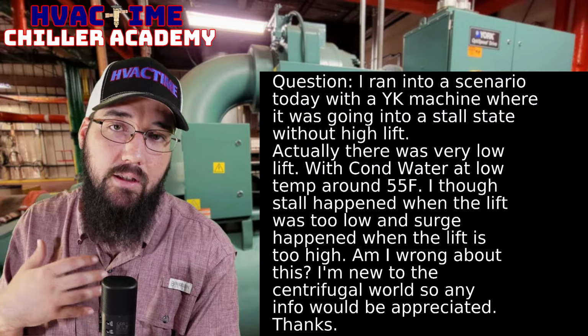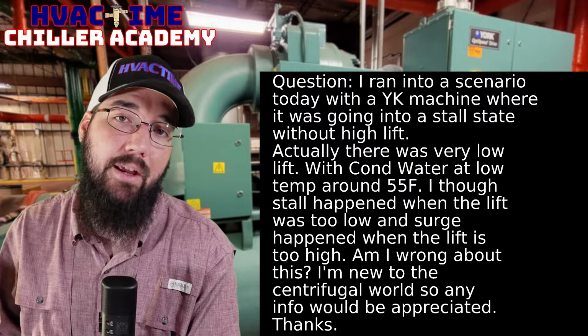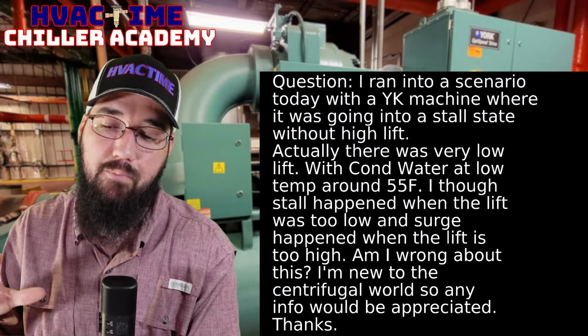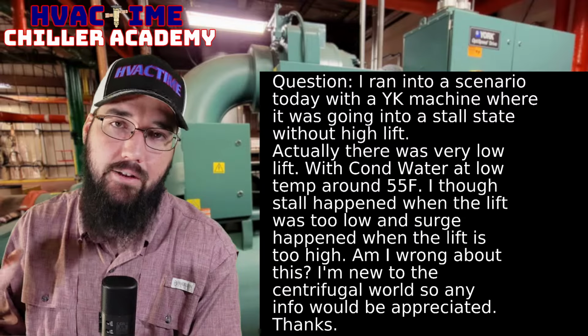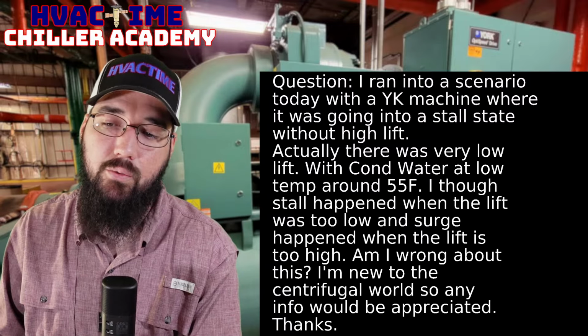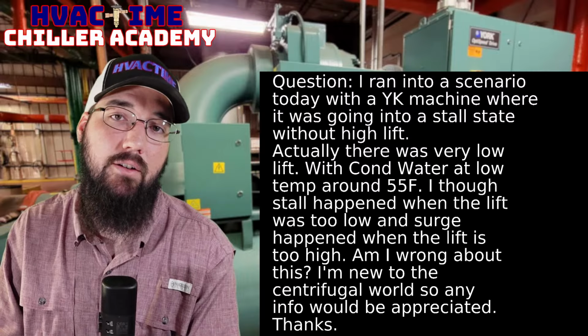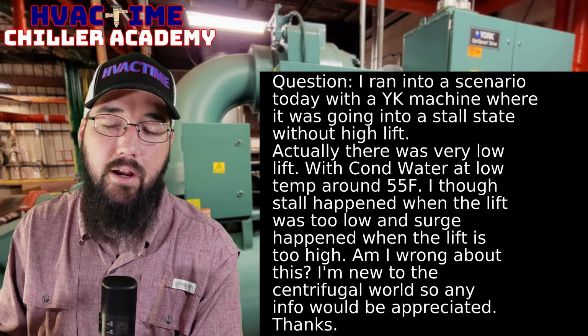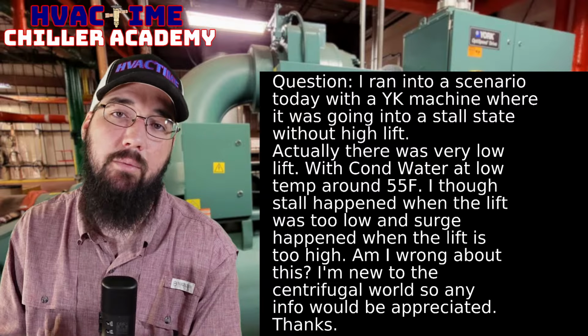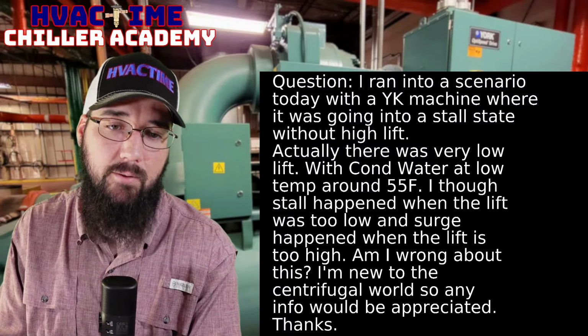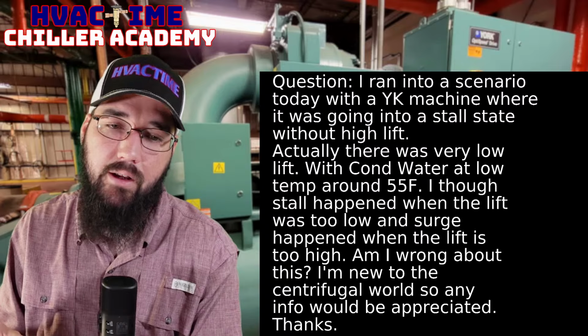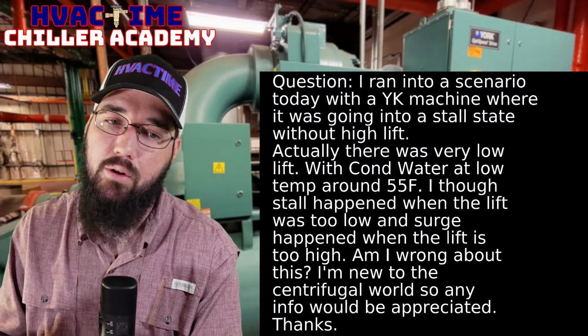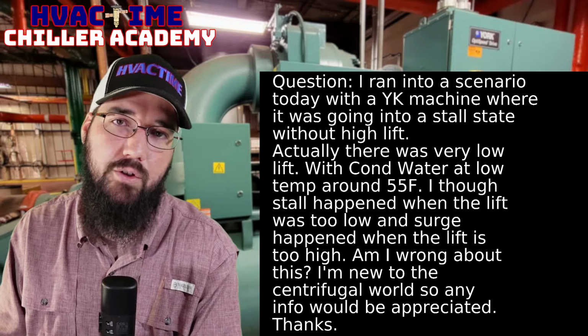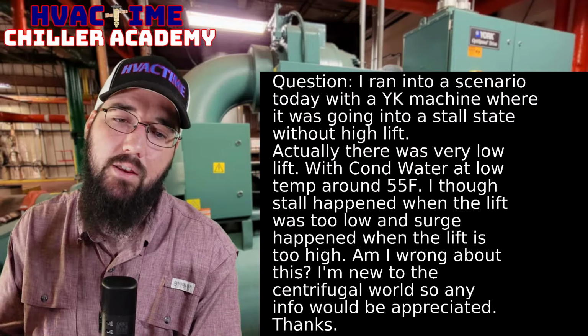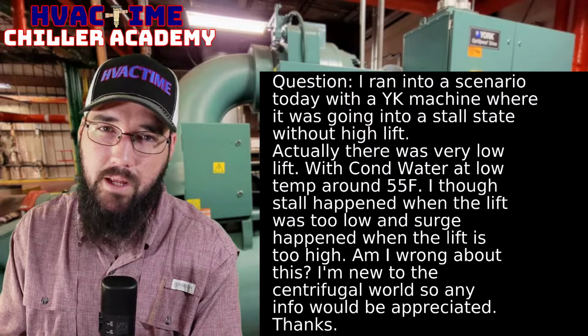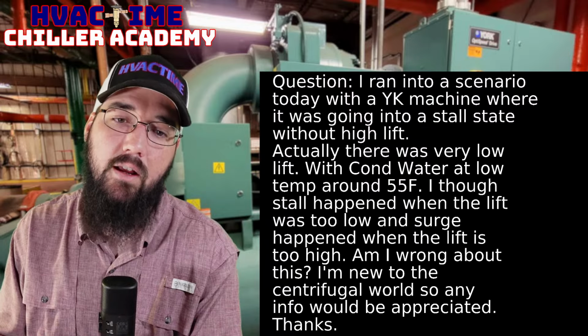I personally don't like running my YKs below 60. 65 was really my kind of default on the low end. There are scenarios where I was fine running down to 60. It was fine, right? As long as we had good control, we had a stable environment. I never liked going below 60. And to my memory, I don't think the YK was supposed to go below 60, or maybe that was the older machines. Maybe the newer models, they say they can go down to 55 condenser water. Maybe I'd have to look that up to verify that.